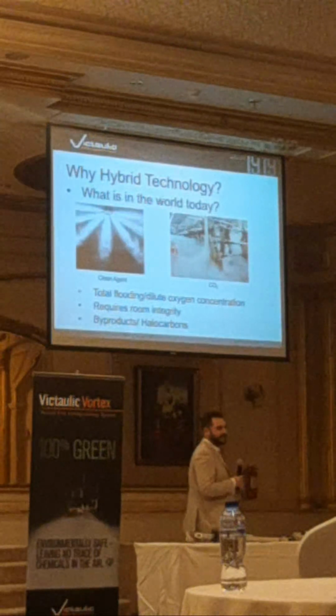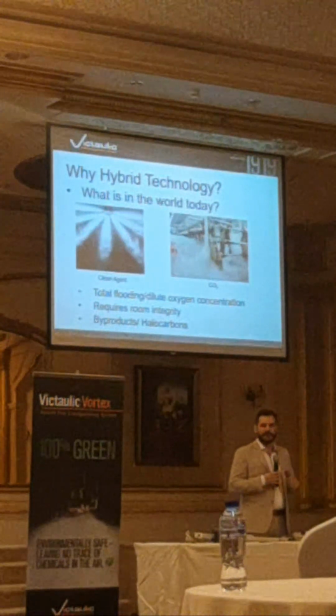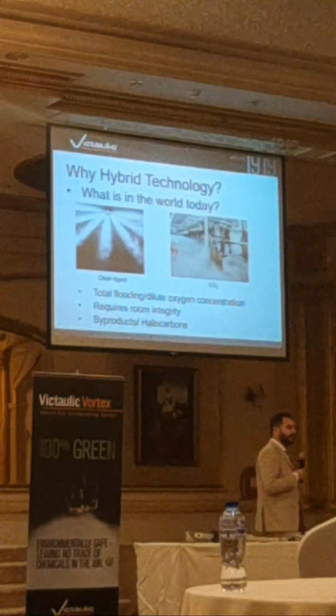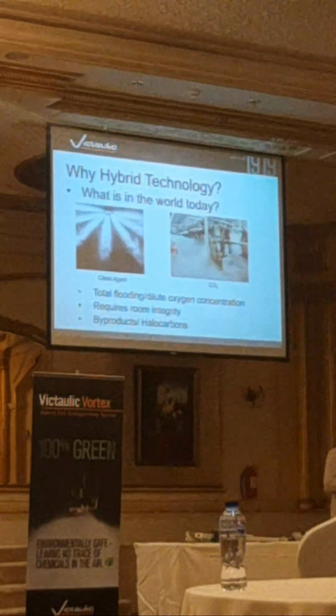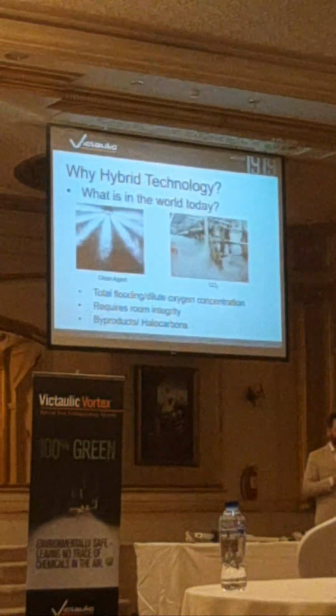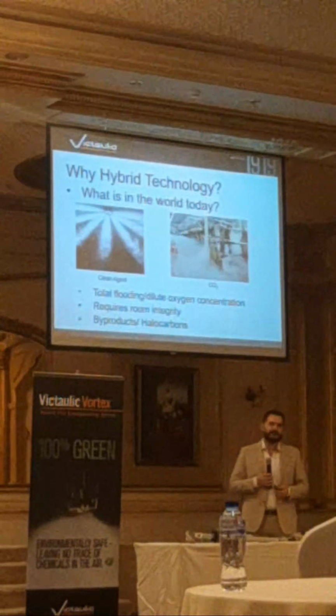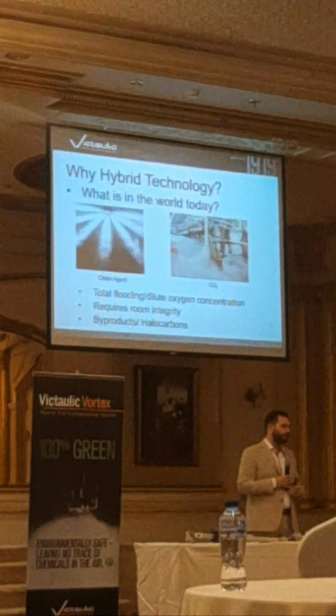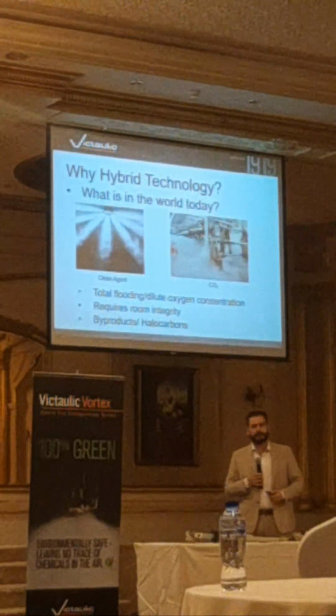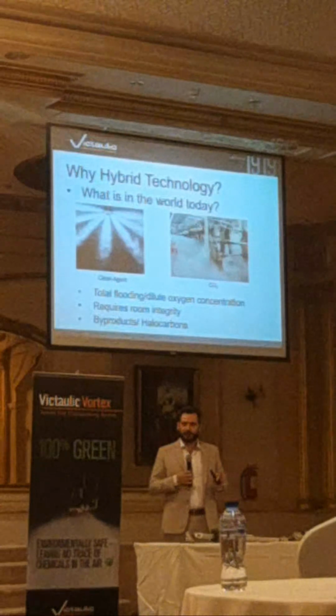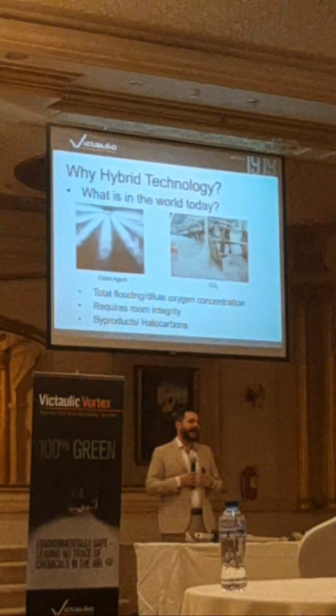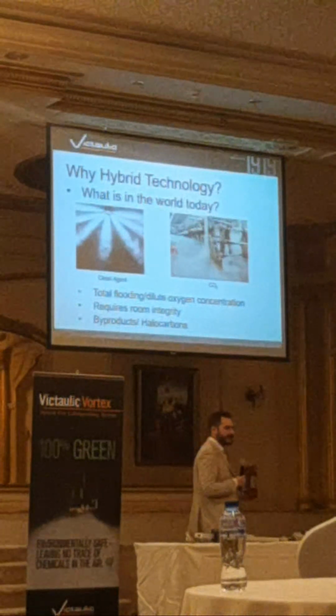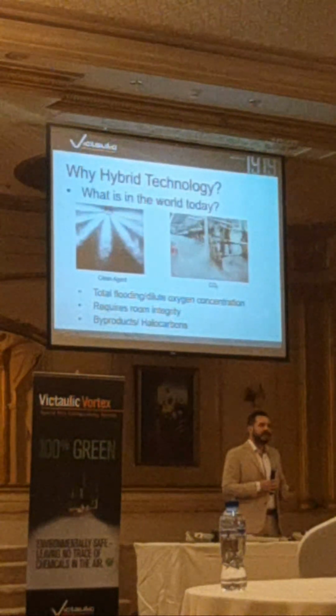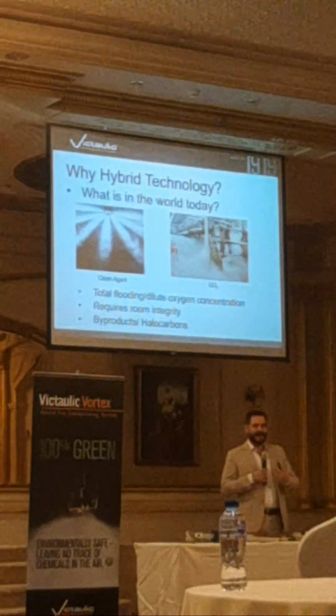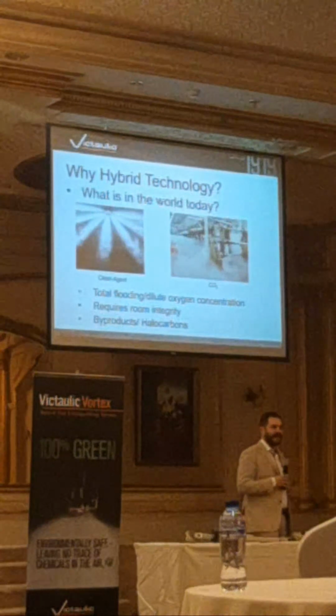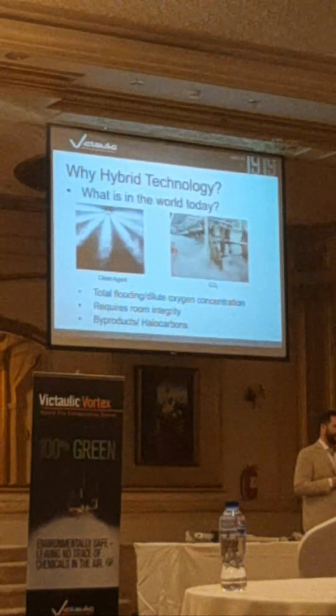Why? Other alternatives will have chemicals. Maybe some of you have noticed that 3M has announced that they're going to discontinue the Novec 1230 due to the PFAS issues that they have in their manufacturing. Also, FM200 is being phased out in Europe, and the Middle East will probably soon follow as well due to environmental reasons. Because we're using pure nitrogen and water, we're using natural resources. So we're not having any sort of global warming effect or ozone depletion, and that doesn't only mean an effect before you have a fire, but also during and after, because you're not going to have any byproducts that can damage the equipment that is inside of your room, inside of your area.